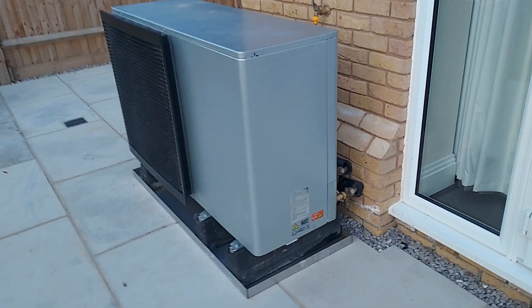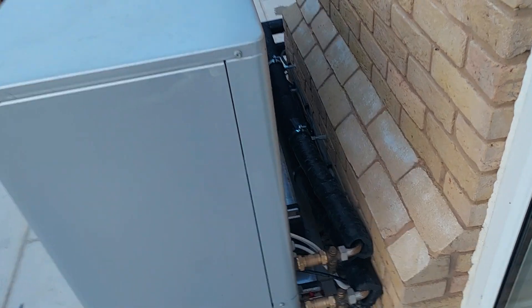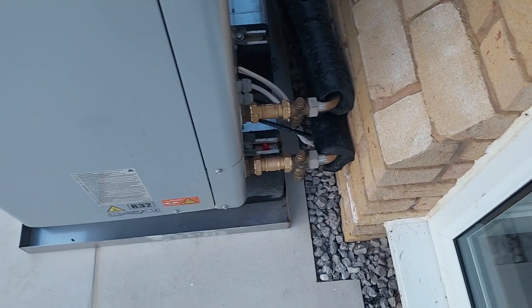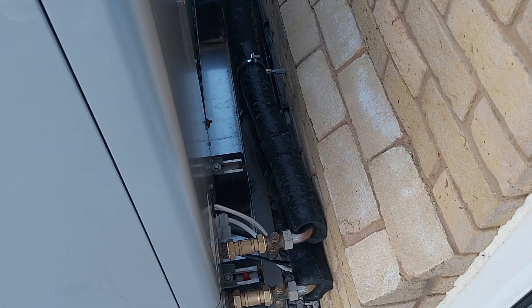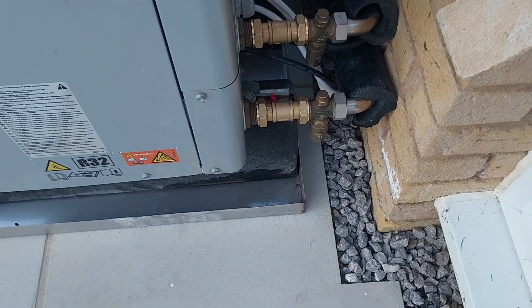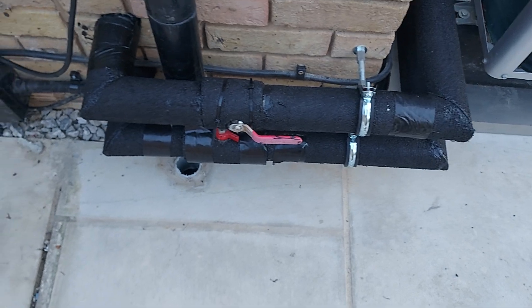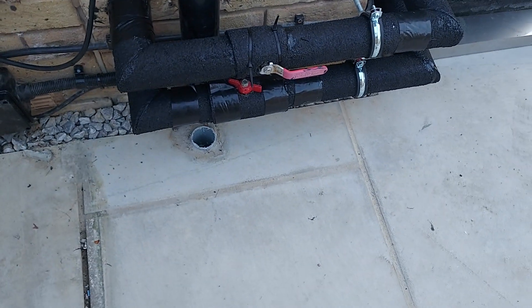One heat pump moved in the tray. I've gone as far back as we can, just pushed it back there. The antifreeze valves are in the correct position, right at the back of the unit — primary pro. Look how much neater that is — it's just a complete contrast to the work done by the contractors. Isolation valve, filter...